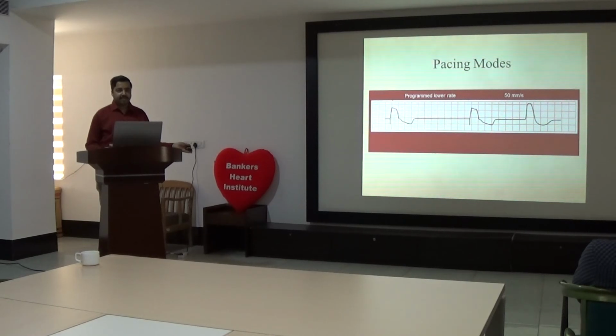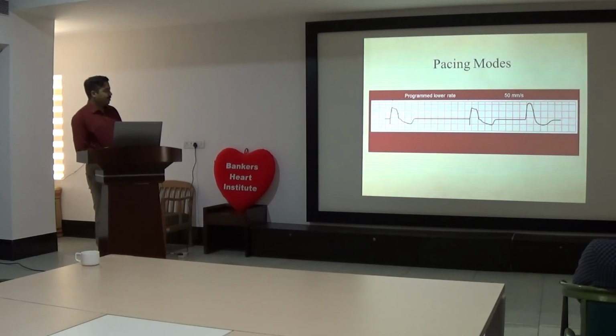The rate is pacing 30. The speed is 50 millimeter per second, so the speed is double, and you have to look at the speed everywhere on the strip. So these two boxes will be one box now. This is 300, 150, 100, 75, 60 and 50. So the rate is around 50. This is the programmed rate. Pacing spike, ventricle captured, pacing spike captured. What is this?